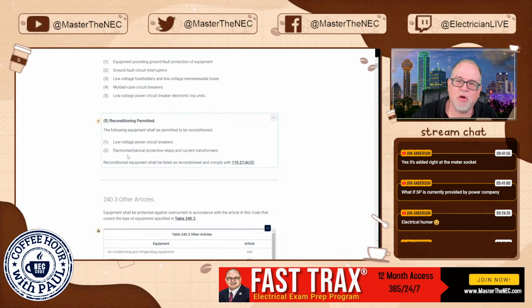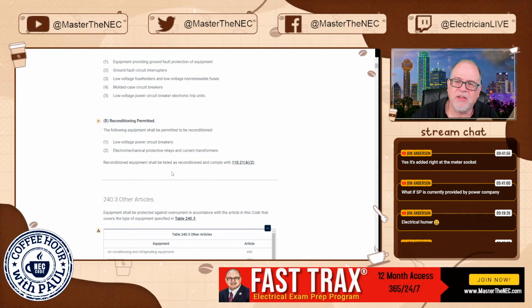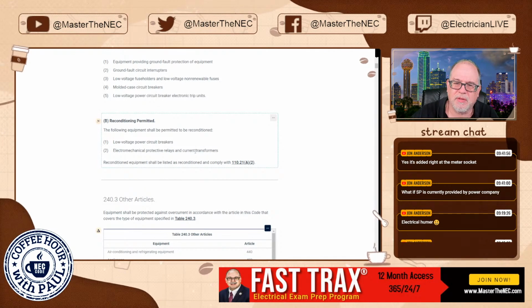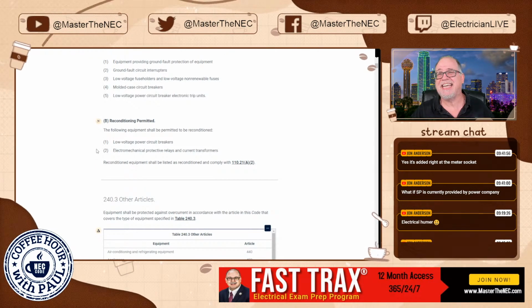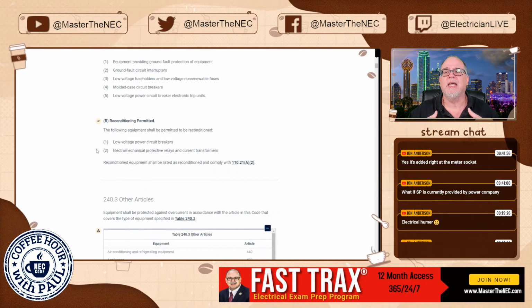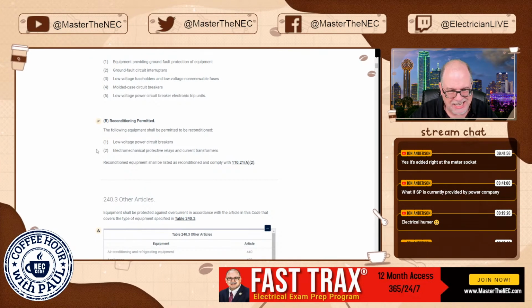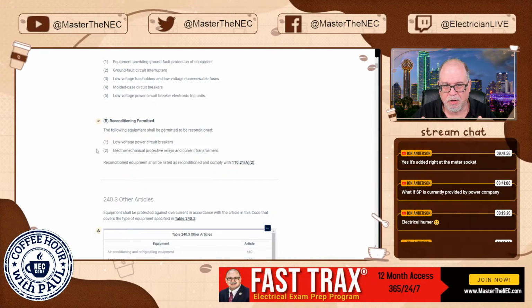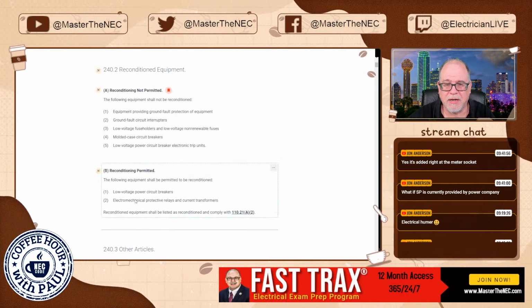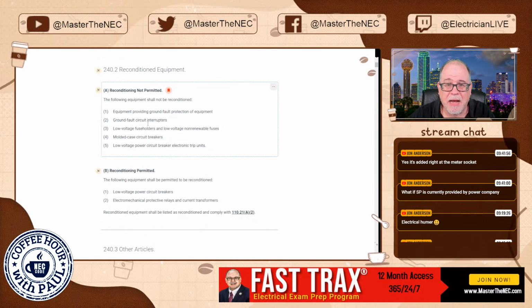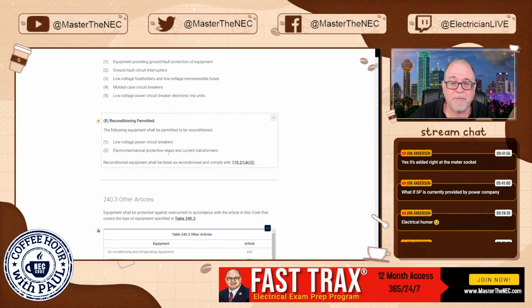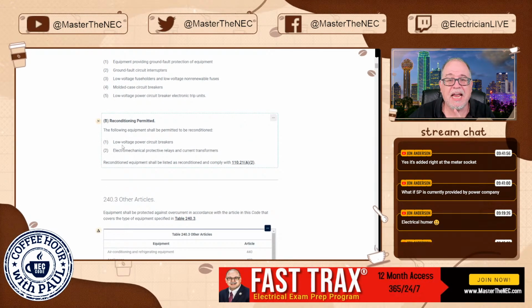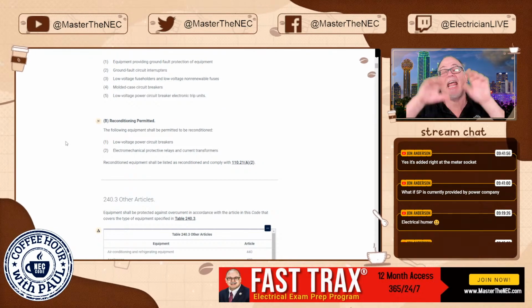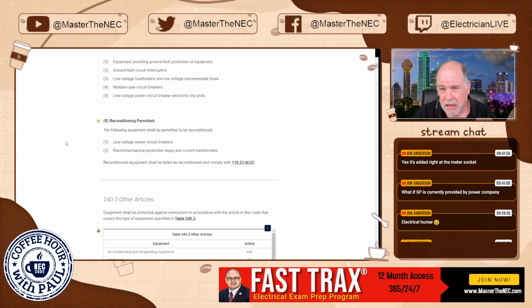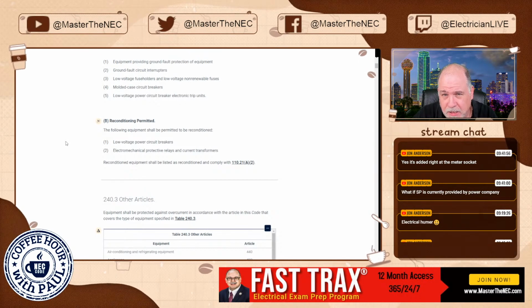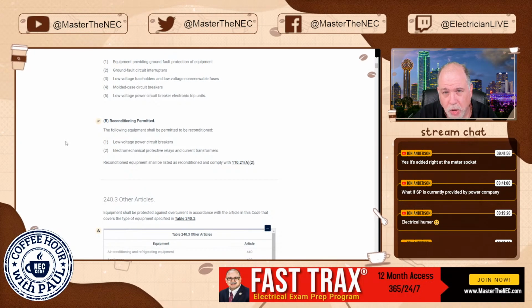Next is electromechanical protective relays and current transformers, okay? If those get exposed, those cannot be reconditioned. You gotta chuck them, okay? Excuse me. These are permitted, I'm sorry, I gotta make sure I'm clear. These are not permitted. These protective relays and current transformers and low voltage power circuit breakers can be reconditioned. All right, you know what? Sometimes you gotta just stop and look at it and say, dude, you're going too fast.